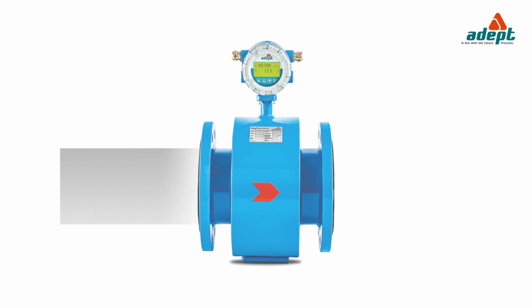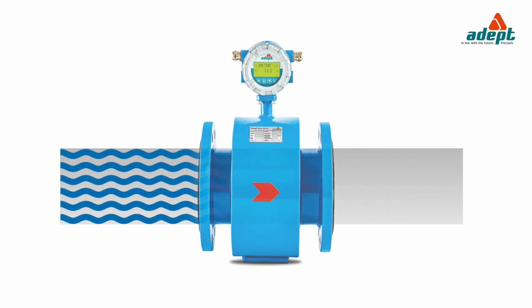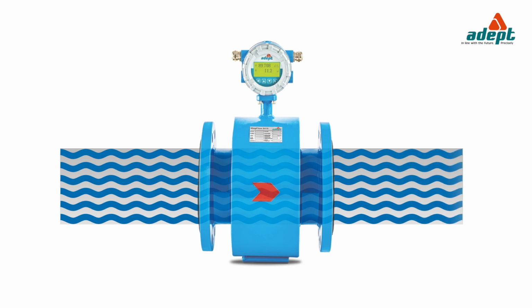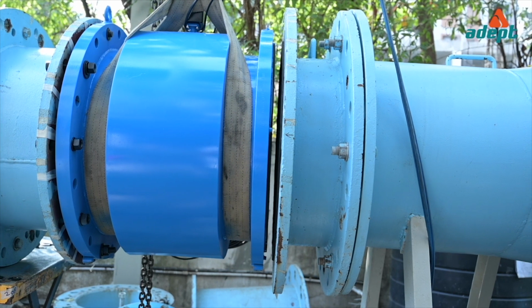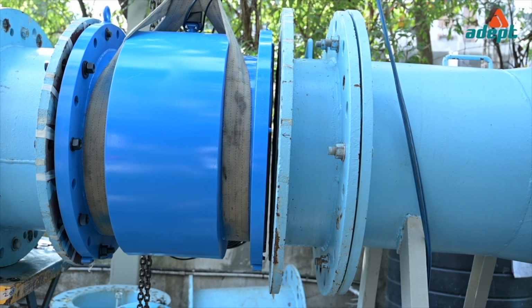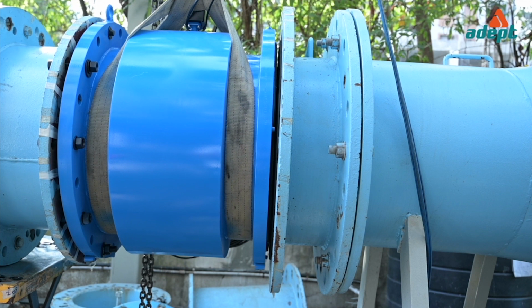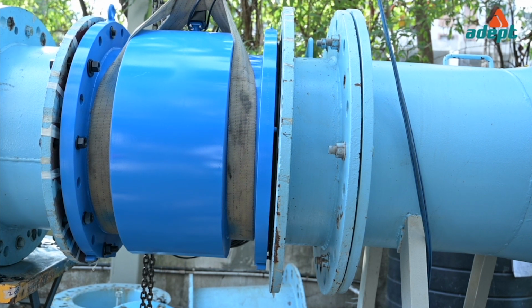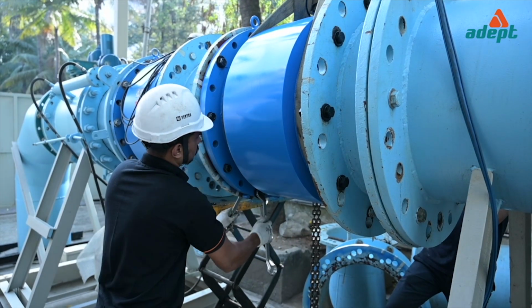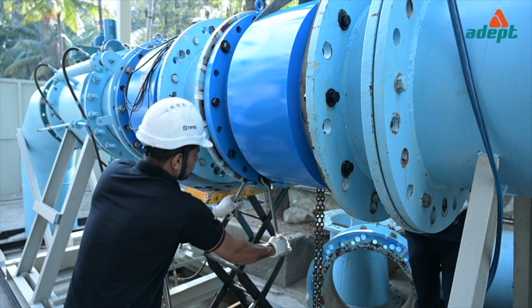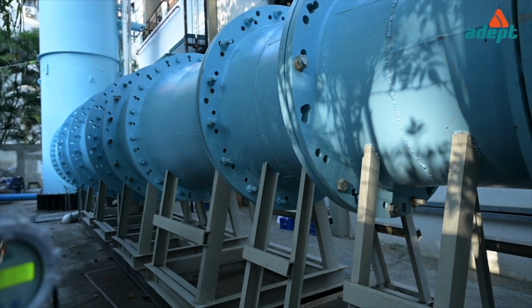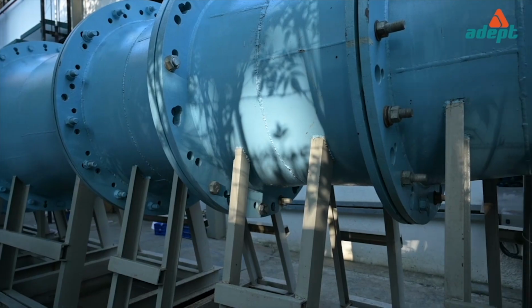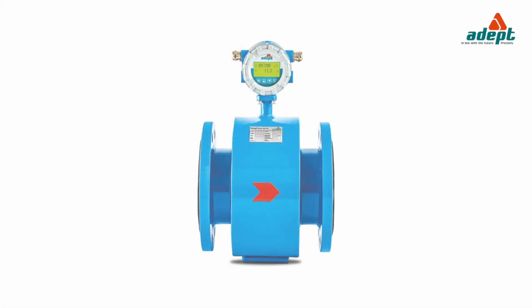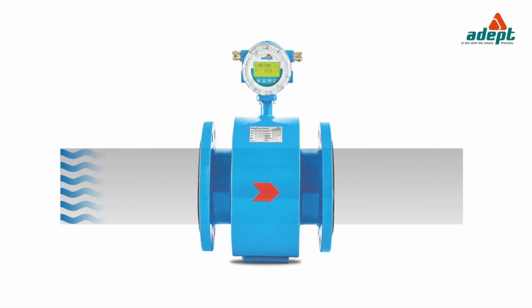Once the flow tube has been mounted, fill the pipeline gradually with water and confirm that the entire mounting is leak-free. If even minor leaks are noticed, check the axial alignment of the flow tube with the upstream and downstream pipe lengths, cleanliness of gasket, the rating of gasket material, and proper tightening of the bolts. After eliminating the leakages, allow the process liquid to pass through the pipeline.